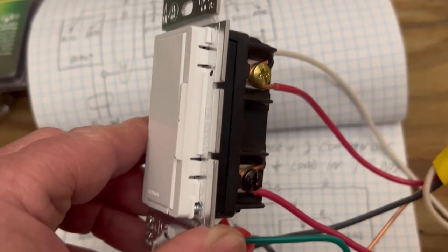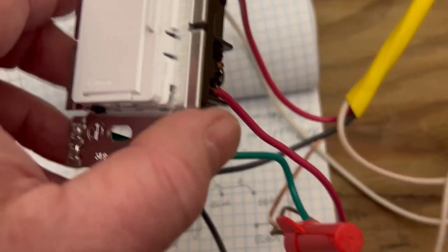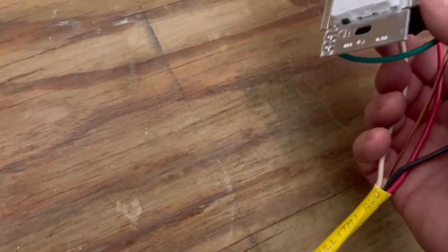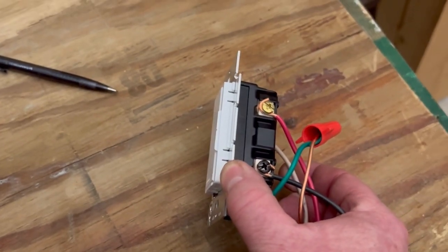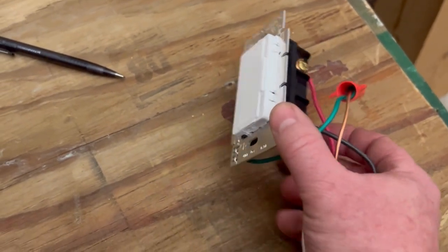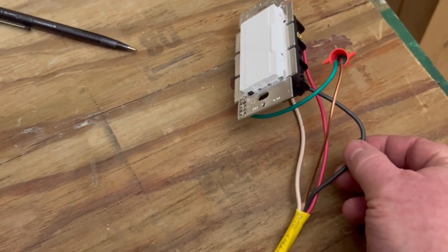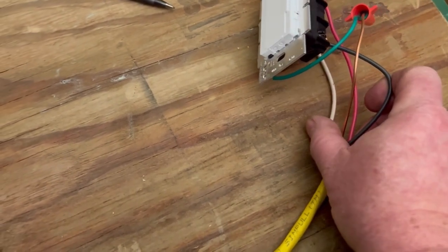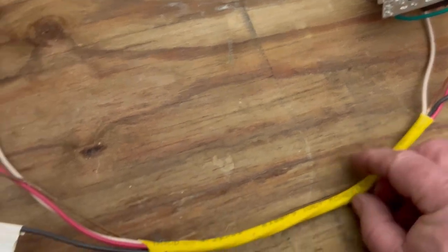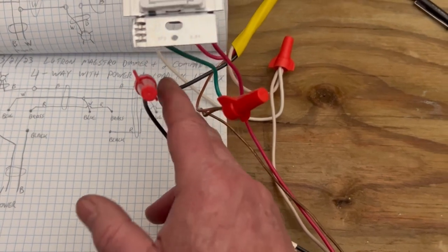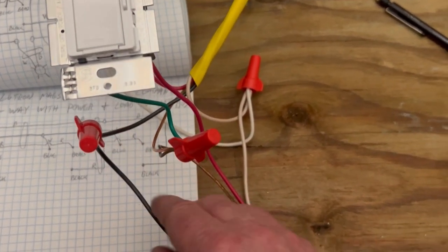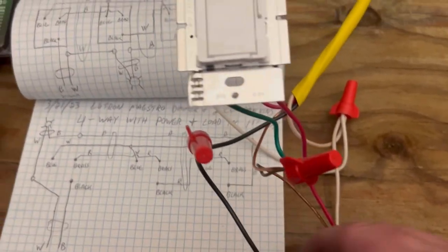Then I'm using the red conductor to go to my second switch, goes to the brass screw on the top there. And then the bottom one, that black screw, using the red wire again, comes out and it goes to the brass screw on that last switch.